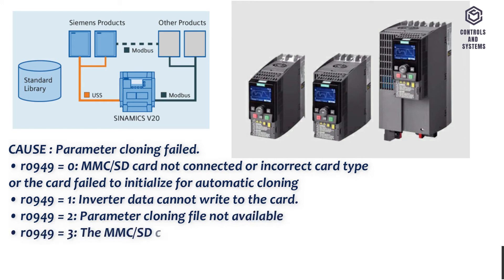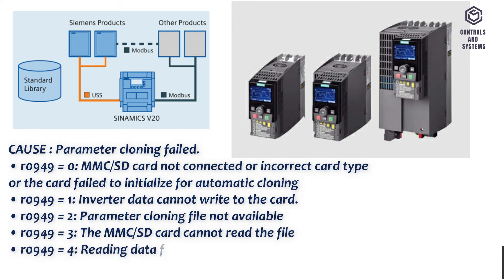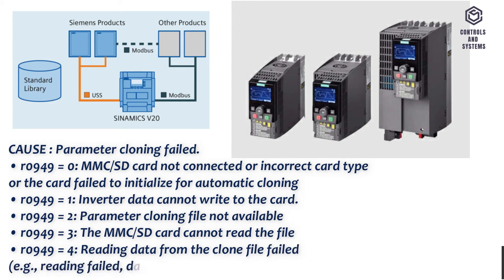R0949 equals 3: the MMC/SD card cannot read the file. R0949 equals 4: reading data from the clone file failed — for example, reading failed, data or checksum wrong.